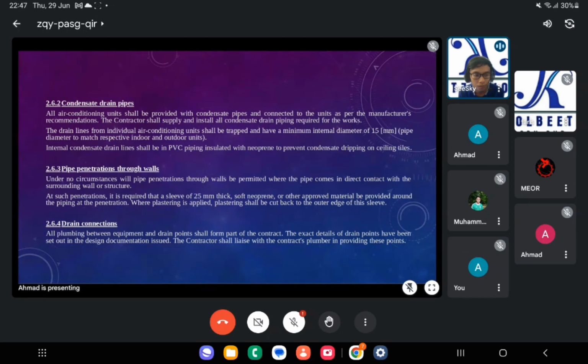2.6.3 Pipe penetration through wall. No pipe penetration through wall shall be permitted where the pipe comes in direct contact with the surrounding wall or structure. Where penetration is required, a sleeve of 25 mm thick soft neoprene or other approved material shall be provided around the piping at the penetration where plastering is applied. Plastering shall be cut back to the outer edge of the sleeve.